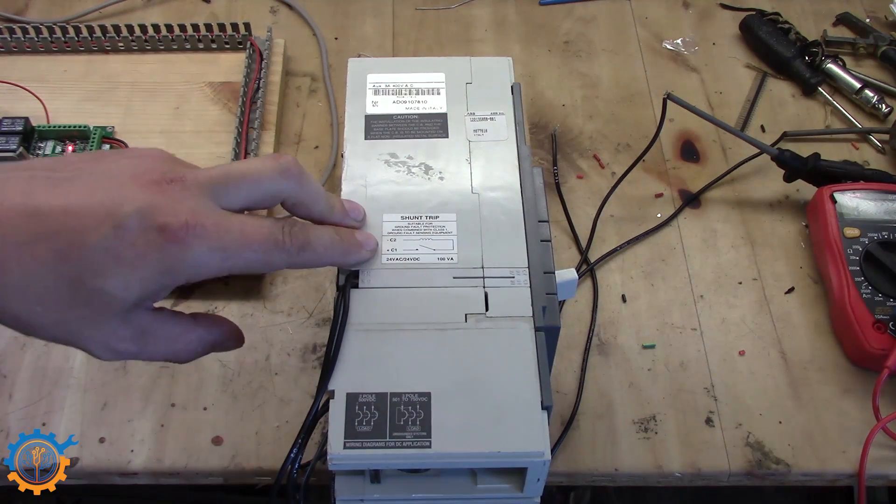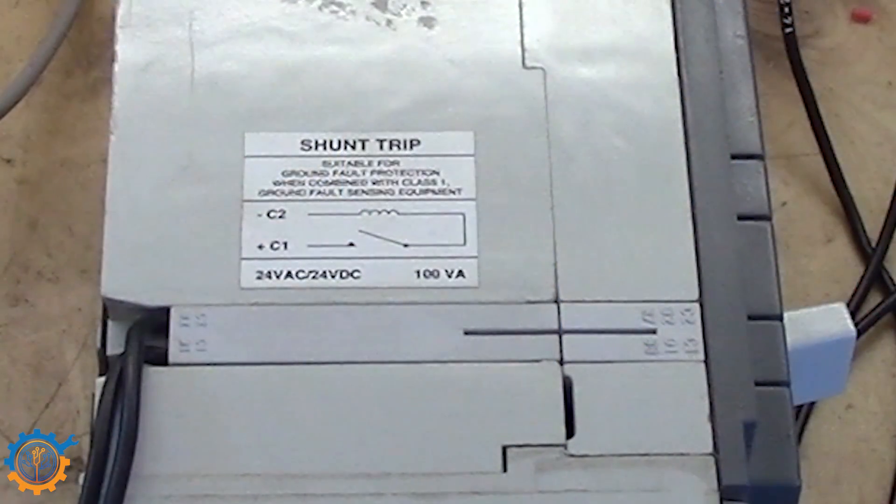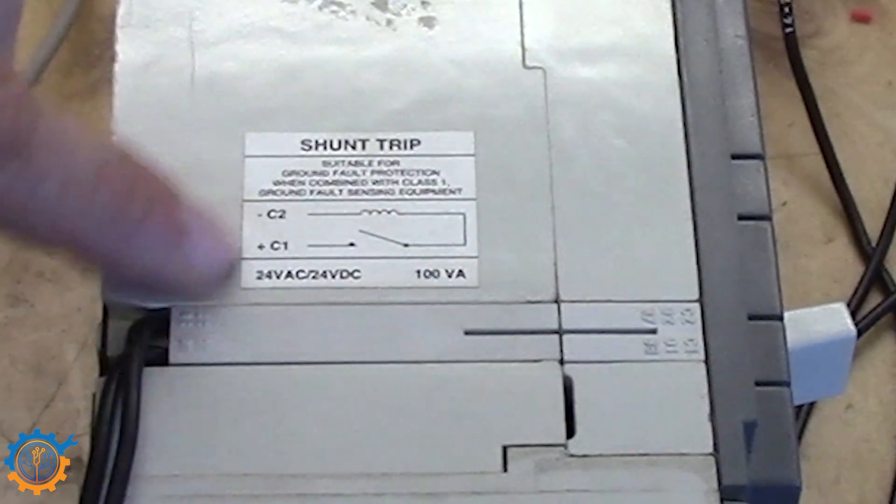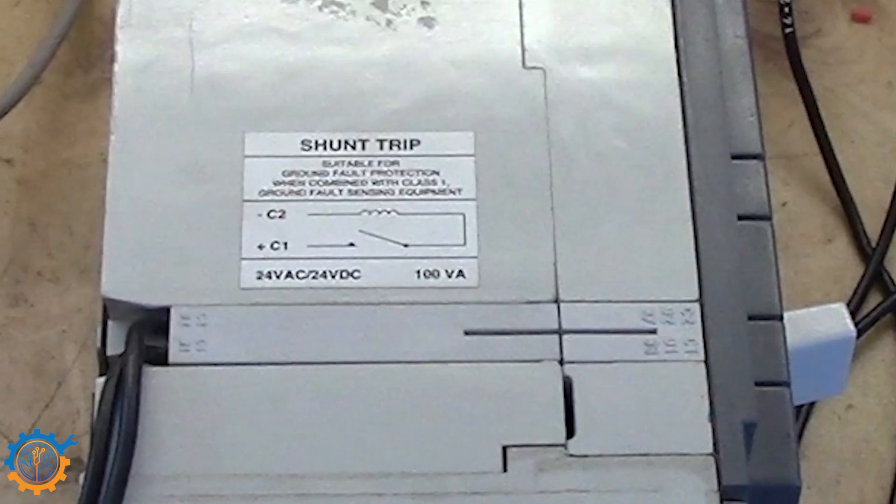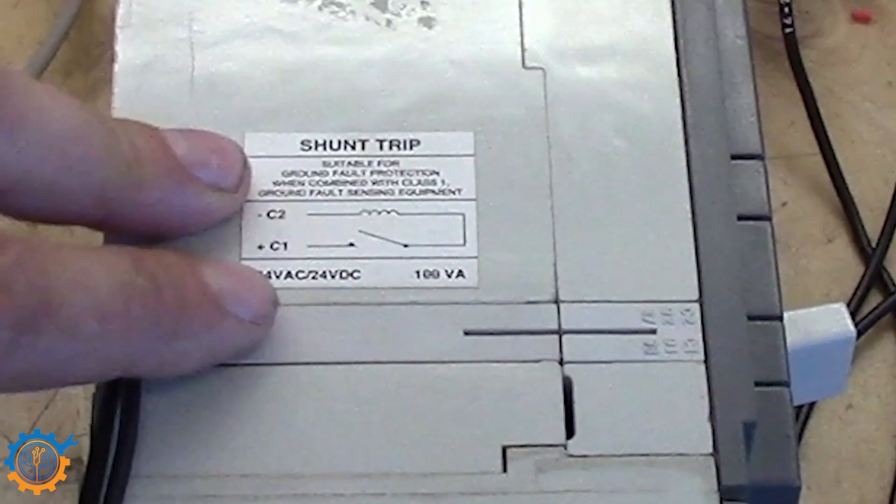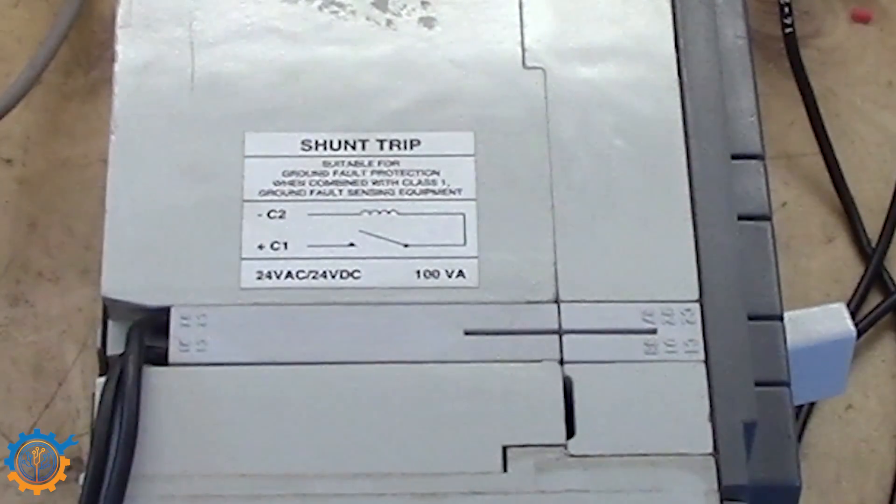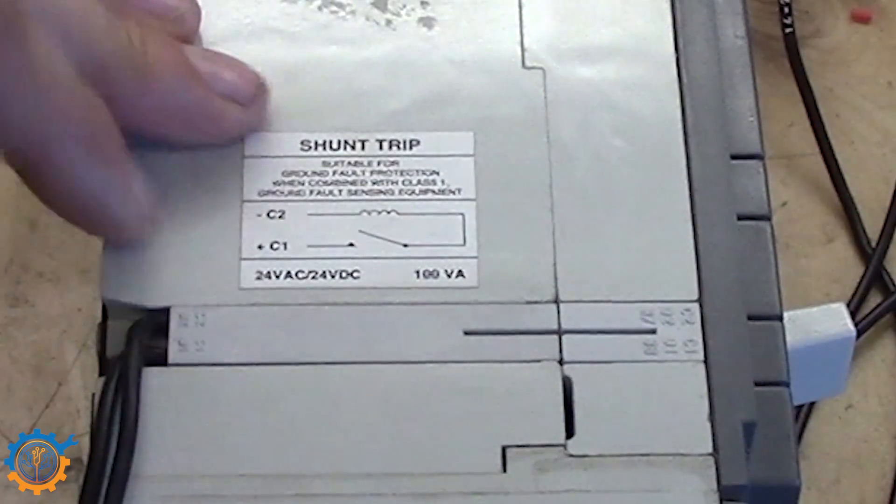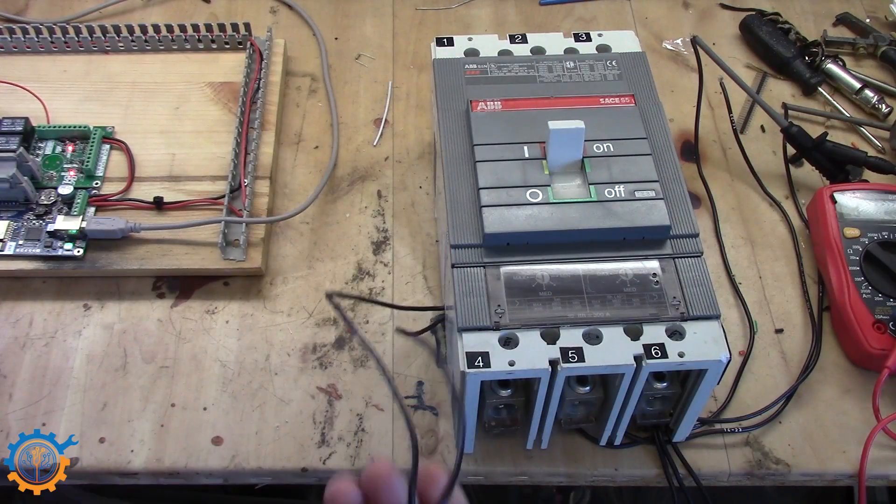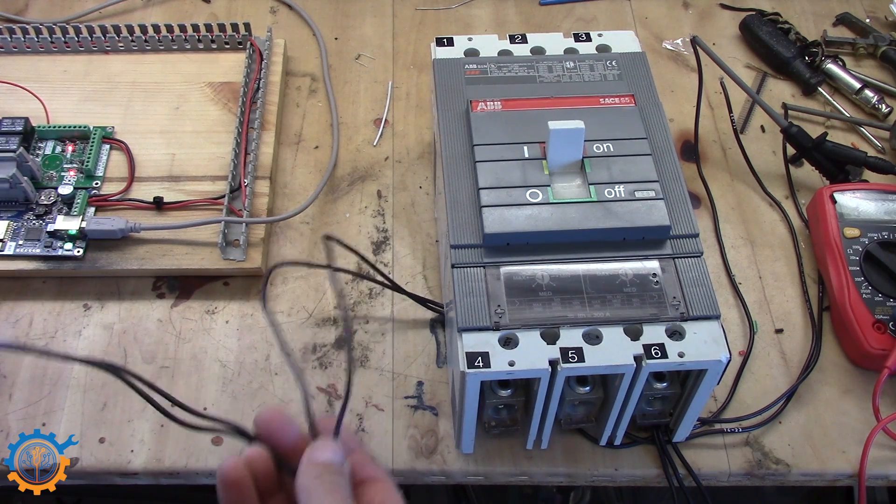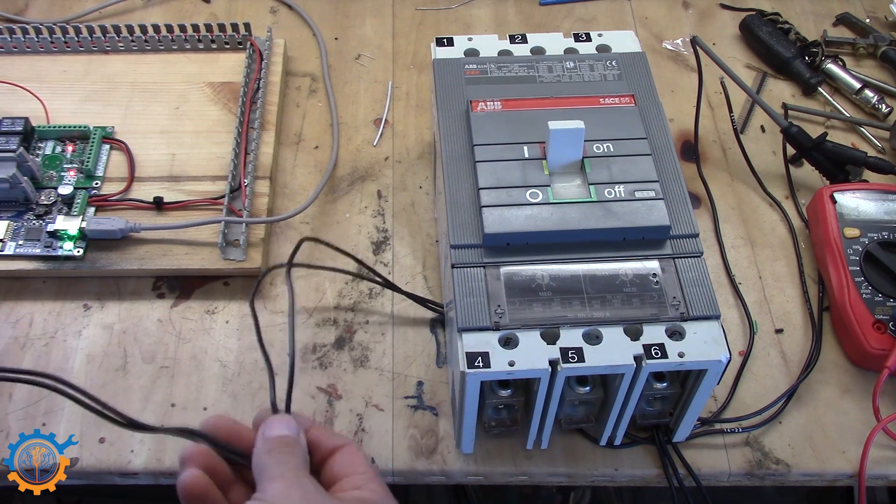This specific model here will need somewhere around 2 amp to trip. So that is important to understand how much current is needed for this to go off. Because it may be that your expansion board will not tolerate this current. And then you need to add an external board to drive this. In this case it does work. So basically we have those two wires here going into the shunt trip. And that is what is going to control it.